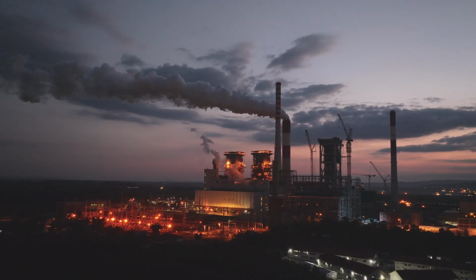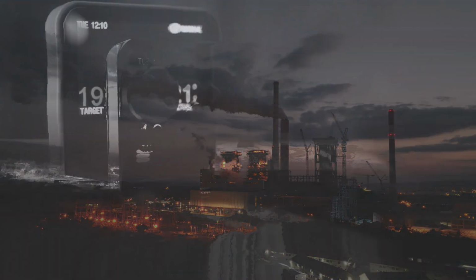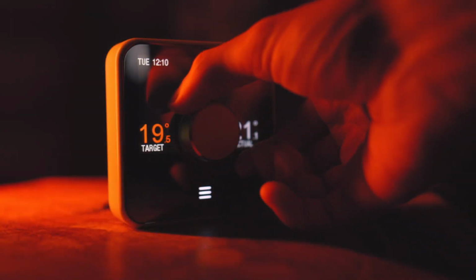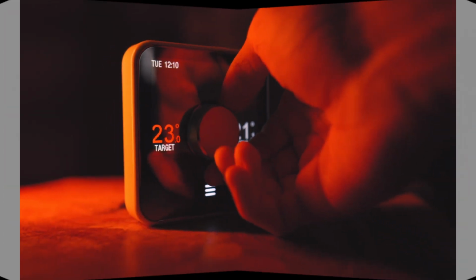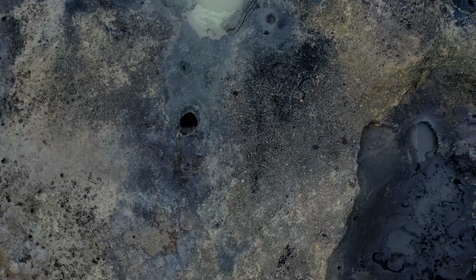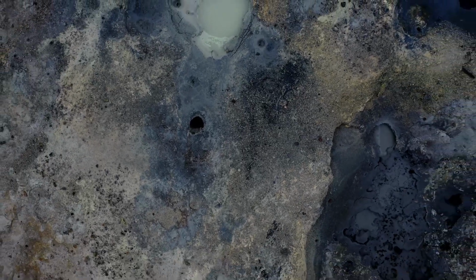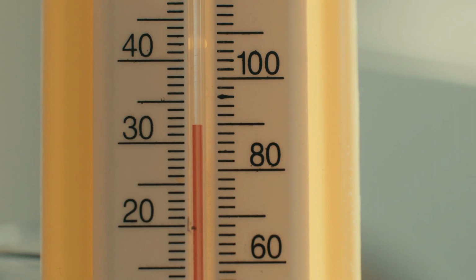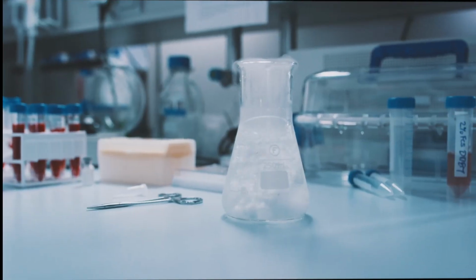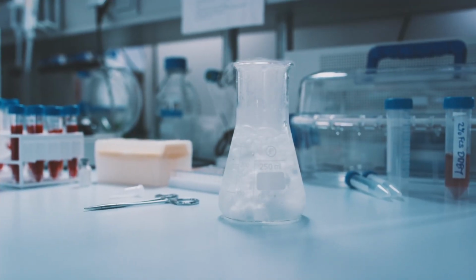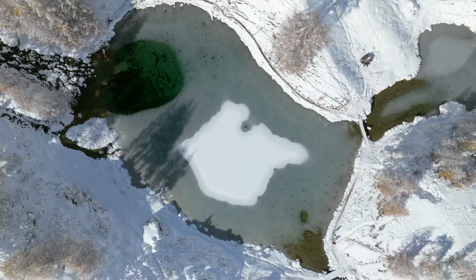What's remarkable about this approach is that it decouples cooling from energy-intensive compression and instead uses passive heat exchange. The rock at 100 meters deep maintains a relatively stable temperature year-round, around 11 to 13 degrees Celsius. But by using winter cold, engineers can push that temperature even lower and turn the ground into a powerful seasonal cold reservoir.